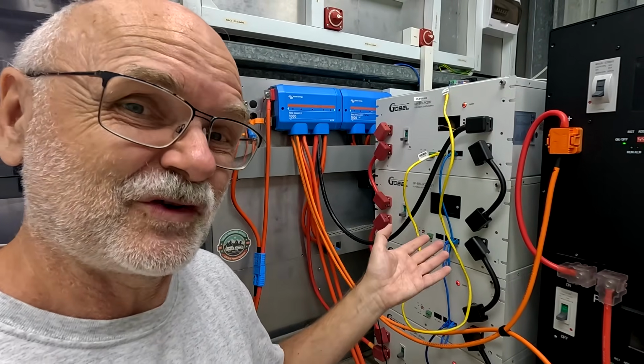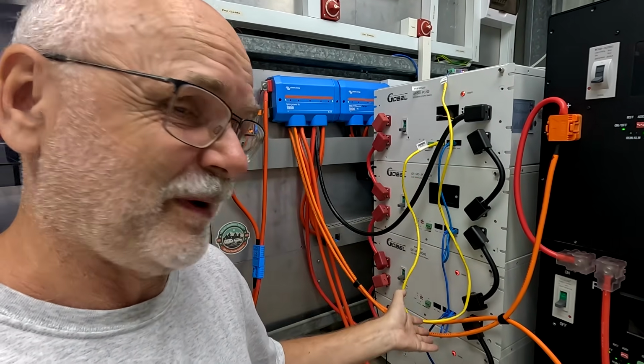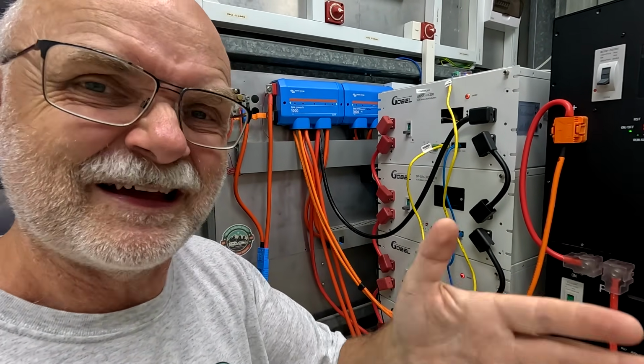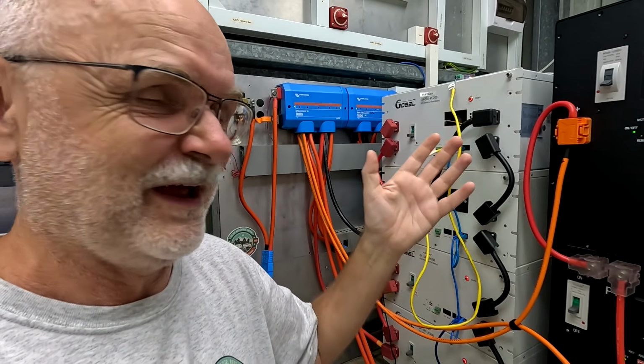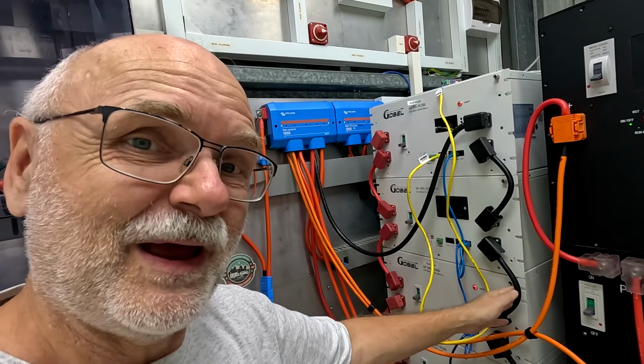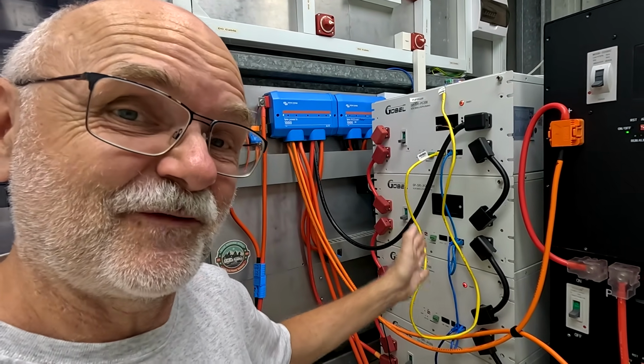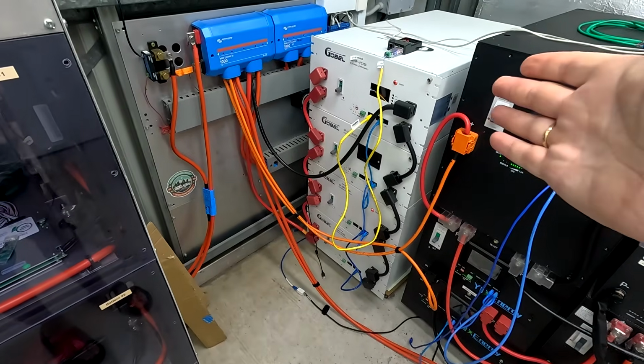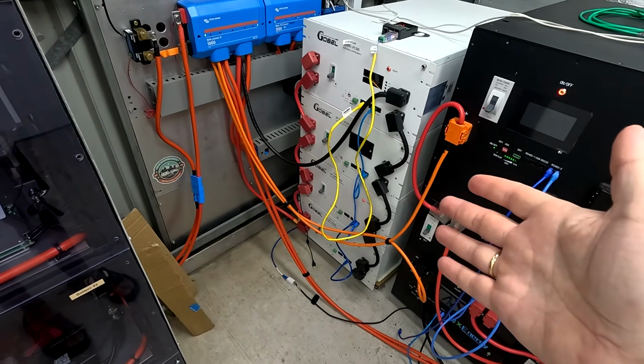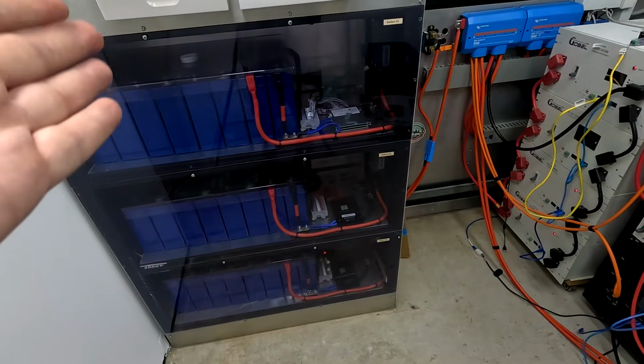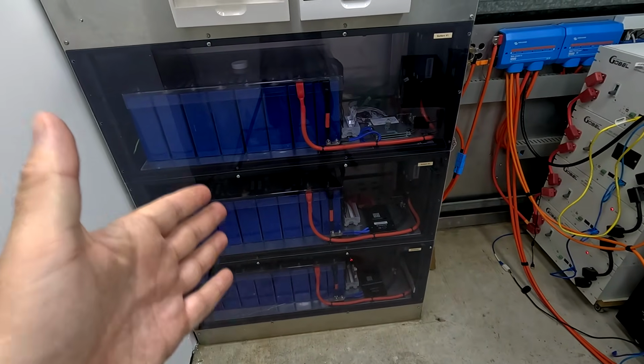And this is pretty much a very typical scenario. You've got 4 batteries here from Gobel Power, Yixiyang, EEL, Seplos, or any other company. You have put them all in parallel, and now you want to connect these 4 batteries to your inverter. I think 3-4 batteries is pretty standard these days. Well, back in the day when we built the battery shelf here, this was actually a huge capacity I built. Most of the users out there had only 1 battery, some had 2 batteries already, and I built a battery shelf with 3 batteries. So 44 kilowatt hours here.